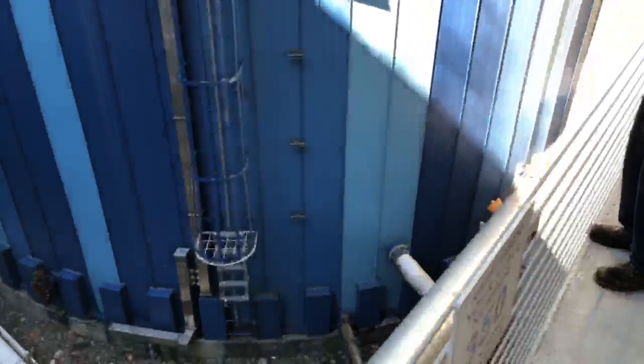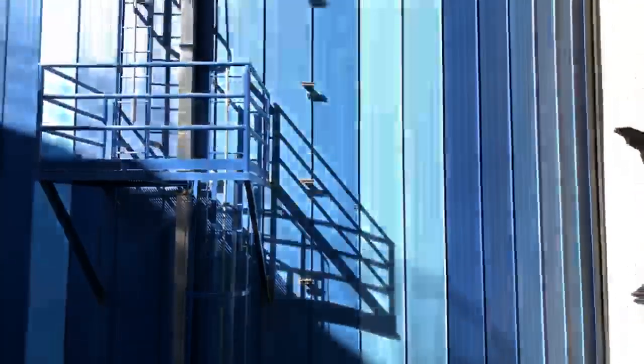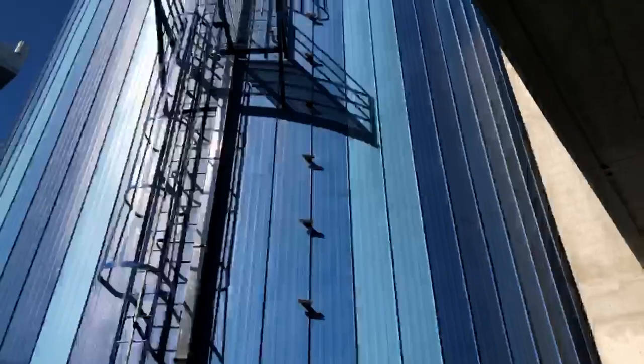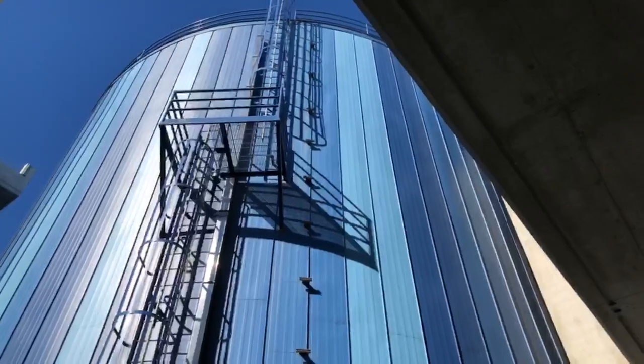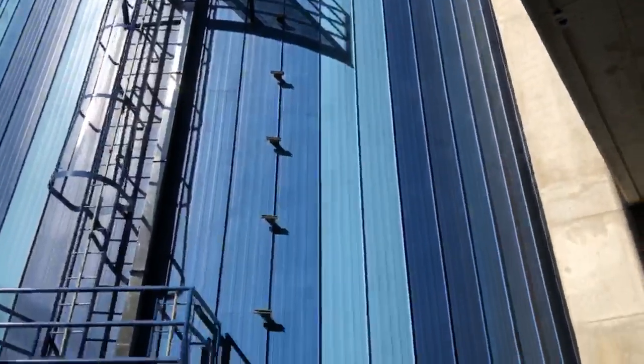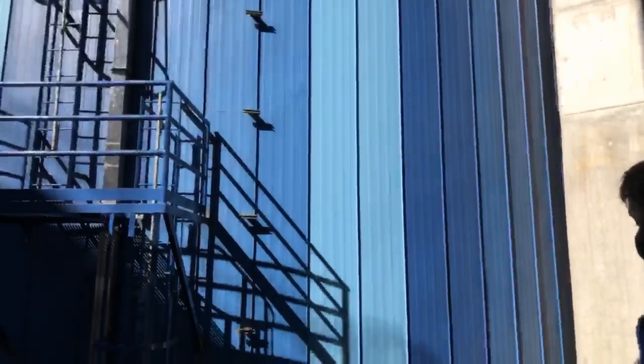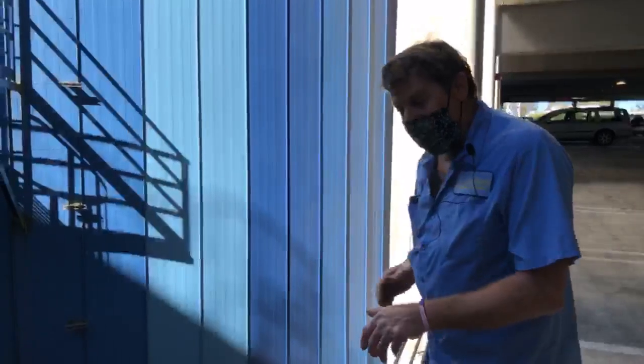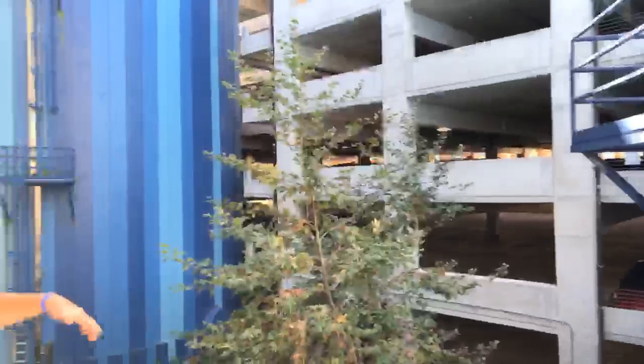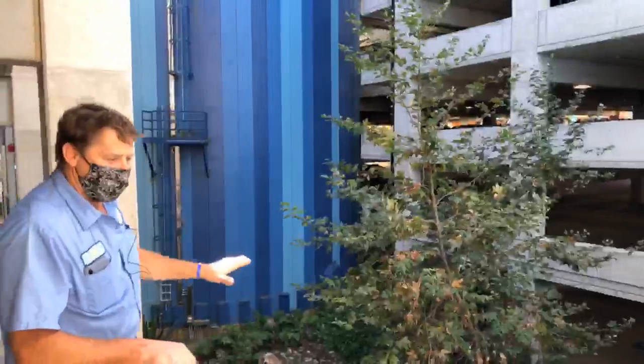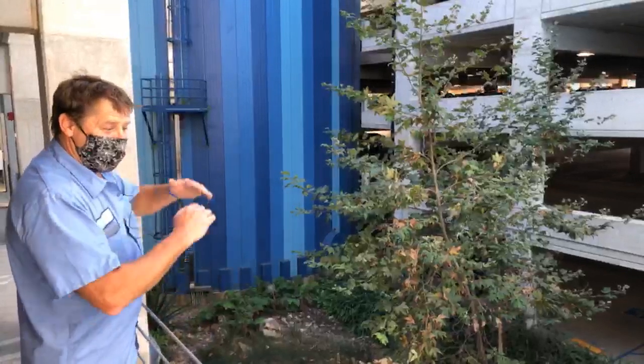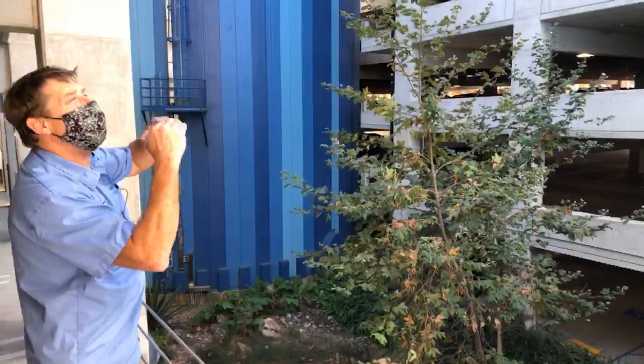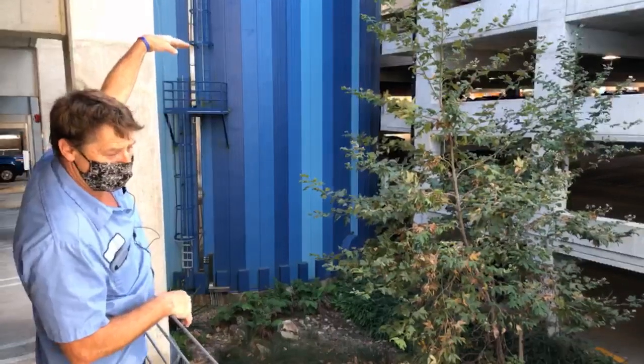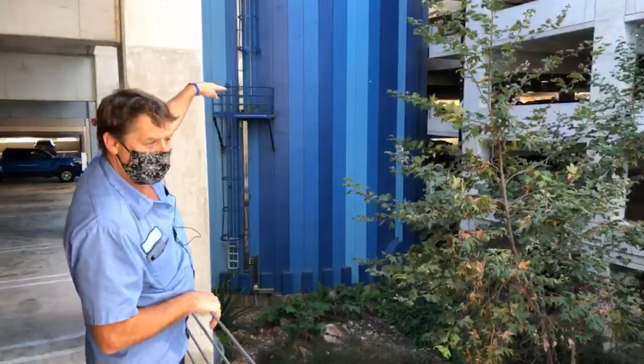There's the same type of distribution header on top, about 6 feet down. It's a PVC pipe that goes the entire circumference inside with holes in it. When you jump into a swimming pool on a hot day without circulation, the surface is warm, but as you go down toward the bottom, or in a lake, it gets colder as you go deeper. That's called a thermocline. Unless you mix it up, there's a fine line, and we can see it clearly here: on top it's 58 degrees, and down below it's 40.